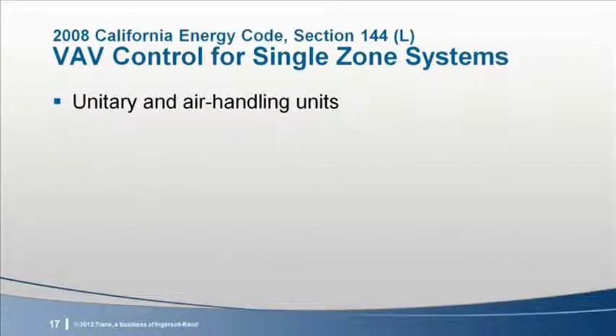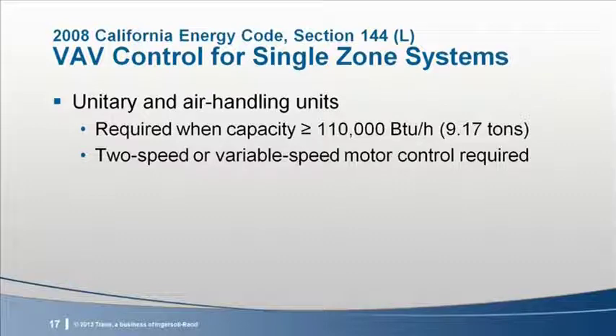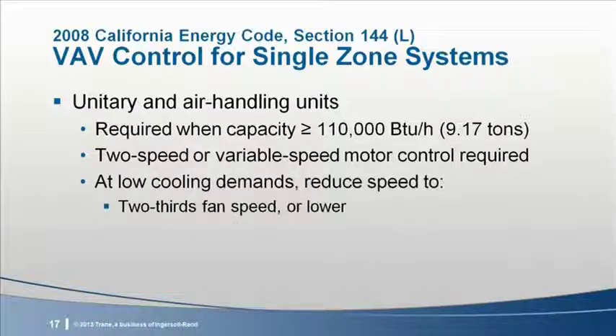The Single Zone VAV requirements, made effective January 1st, 2012, are similar to those presented in ASHRAE Standard 90.1. Section 144L requires Single Zone VAV control within the prescriptive requirements. The section states that all unitary and air handling units which serve a single zone with an ASHRAE rated cooling capacity of at least 110,000 BTU must be served by a variable volume supply fan controlled by either a variable speed drive or a 2-speed motor. At low cooling demand, the supply fan motor must reduce speed to a minimum of 2/3 of design speed. Delivery of ventilation air must be maintained based upon the requirements of Section 121.